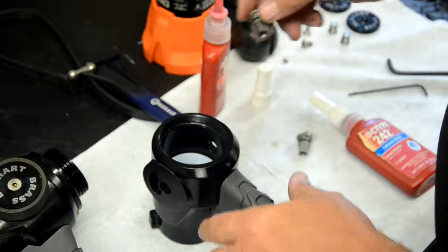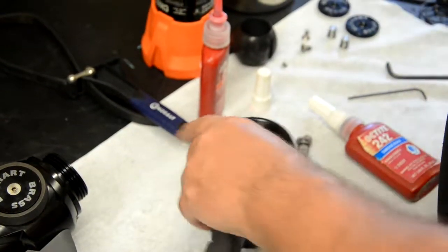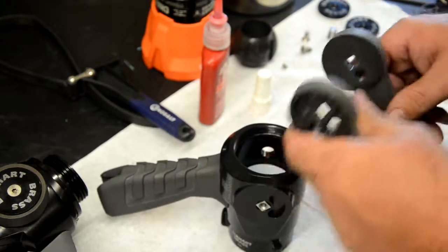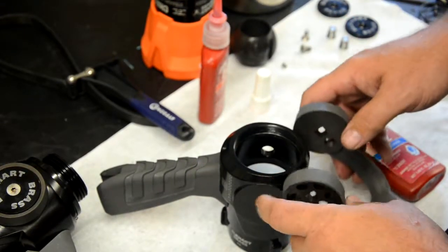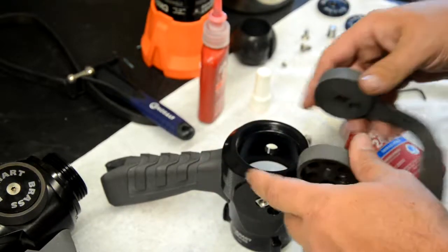We're now going to reinstall the bale handle. Place the bale handle back into the shutoff body in the open or back position at approximately 45 degrees. Note, make sure the word open on the bale handle reads from the discharge side of the shutoff body.